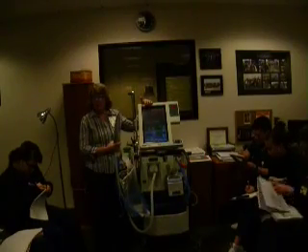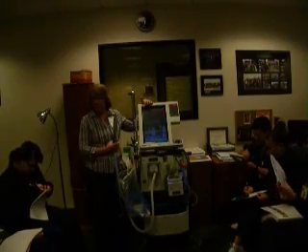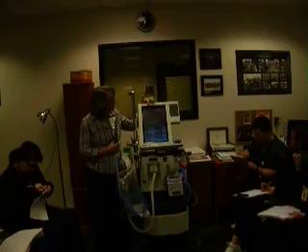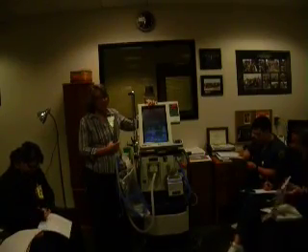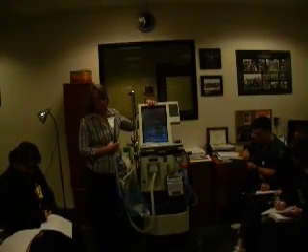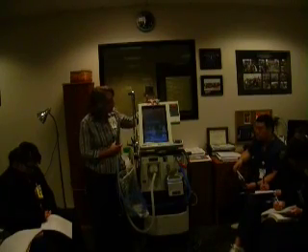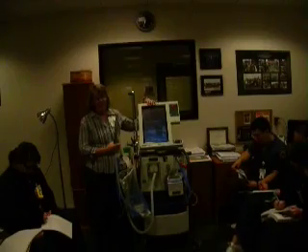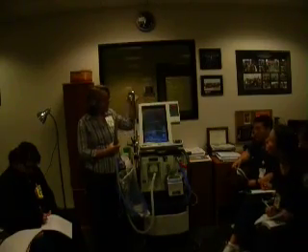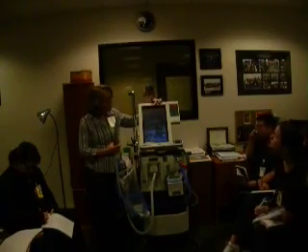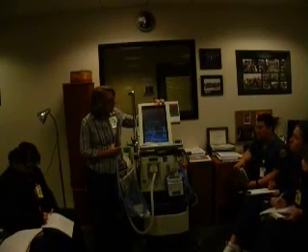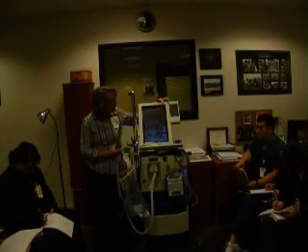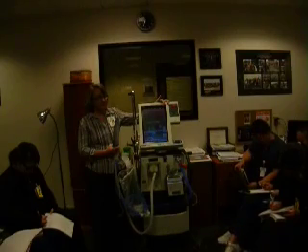That's like your PIP, that's your maximum pressure that's reached with each breath. P mean, mean airway pressure. PEEP, this is your actual PEEP reading. Remember, these are actual numbers. This is what we set. Here's what is actually happening. Your I to E ratio, your rate, your tidal volume, and your minute ventilation.